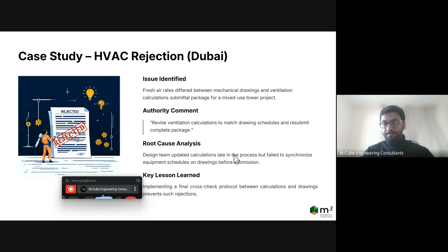If it is 350.50, ensure that 0.50 is mentioned on the riser diagram as well as on the calculation. Even if you have an extra decimal point like 0.500 or 0.501, because of that extra 0.001, he can reject the file. This has happened even for HVAC as well as for electrical projects. So try to always use round figure numbers so that it's easy for the authority to review and give you the approvals.